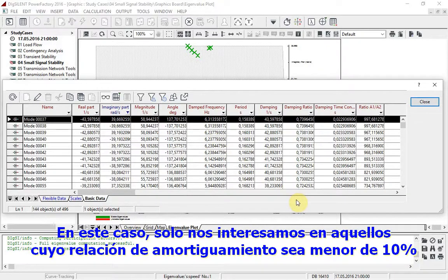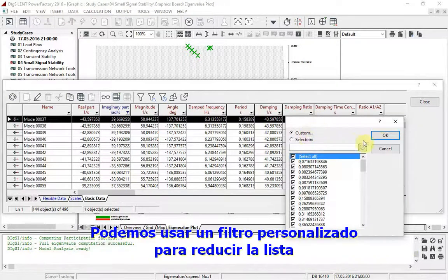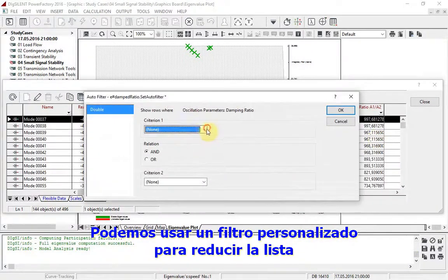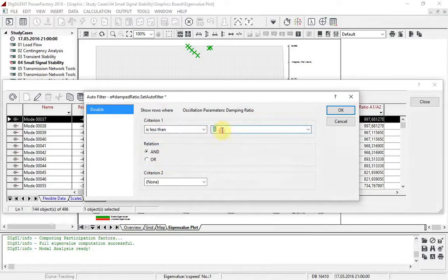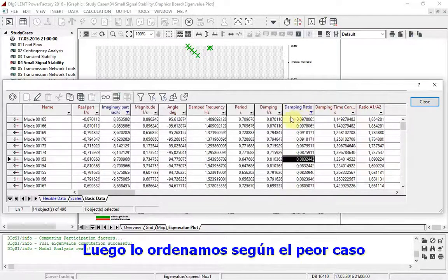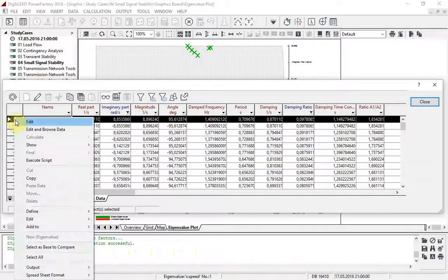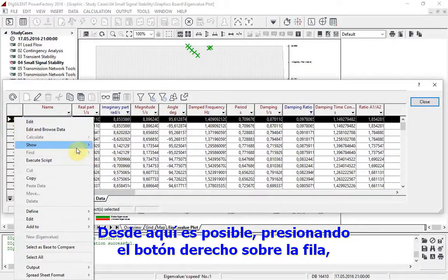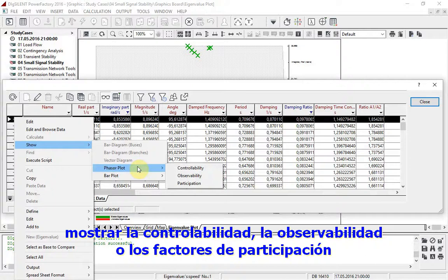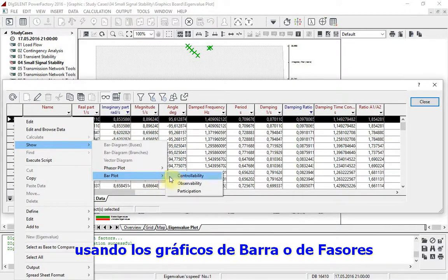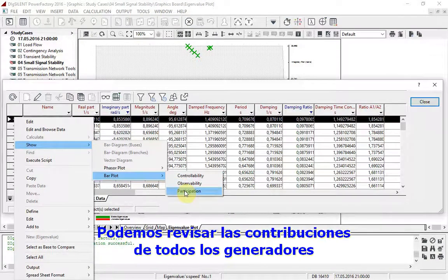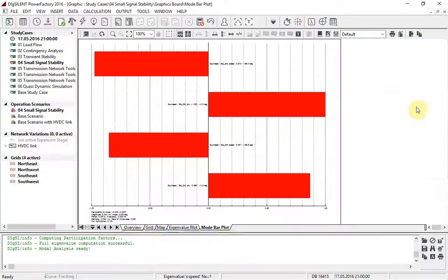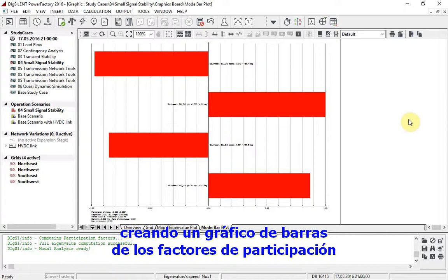In this case, we are only interested in those where the damping ratio is less than 10%. We can use a custom filter to reduce the list accordingly. Then we can sort to see the worst case. From here it is possible, by right clicking on the row, to show the controllability, observability, or participation factors using bar plots or phasor plots. We can look at the contributions of the various generators by creating a bar plot of participation factors.